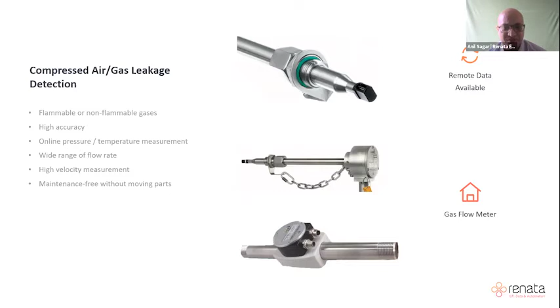Then compressed air leakage - this is a major energy consumer in any factory. So seeing the efficiency of the compressor and ensuring there are no leakages happening in the distribution system - we put up flow meters at various places to help you do that.